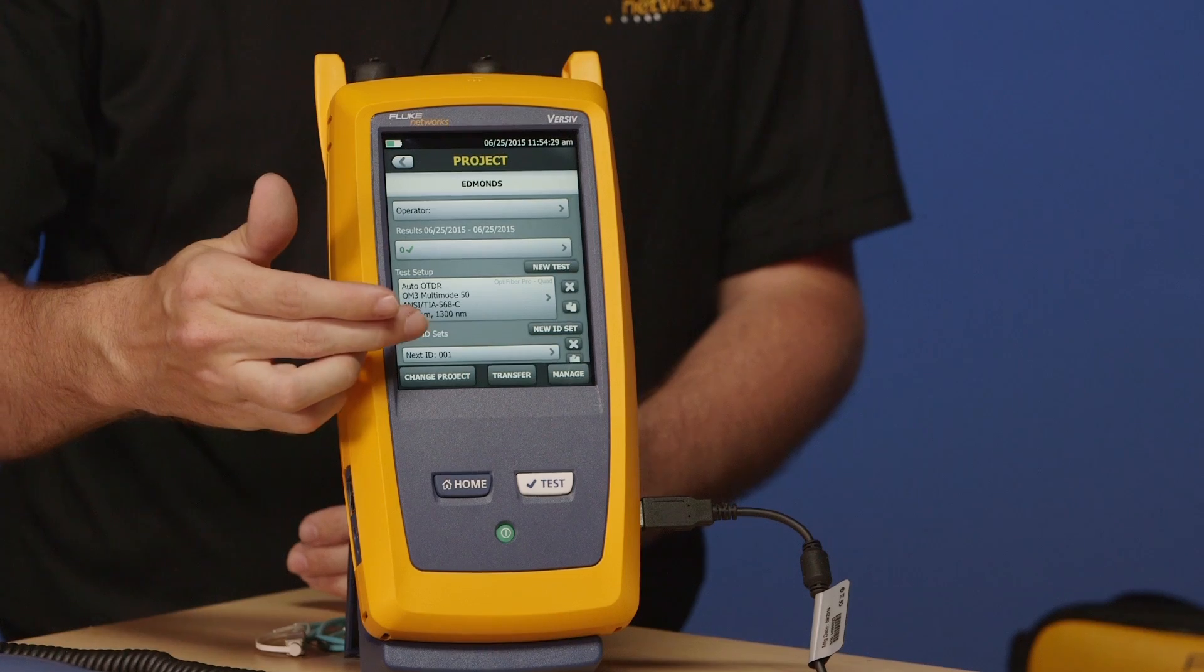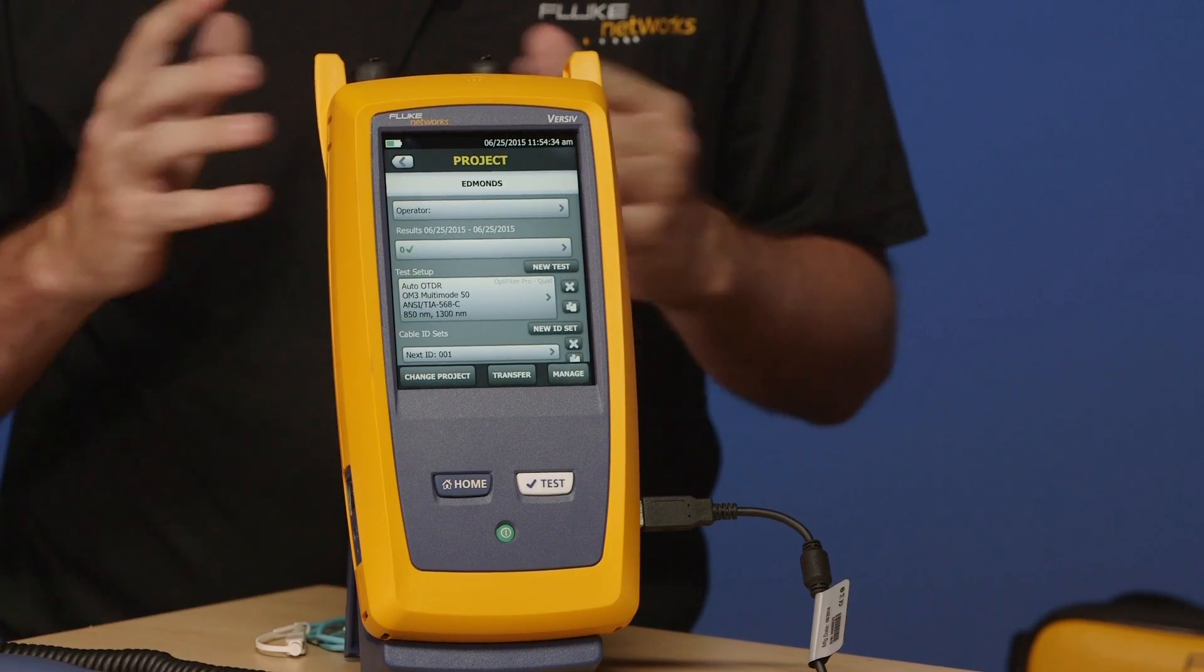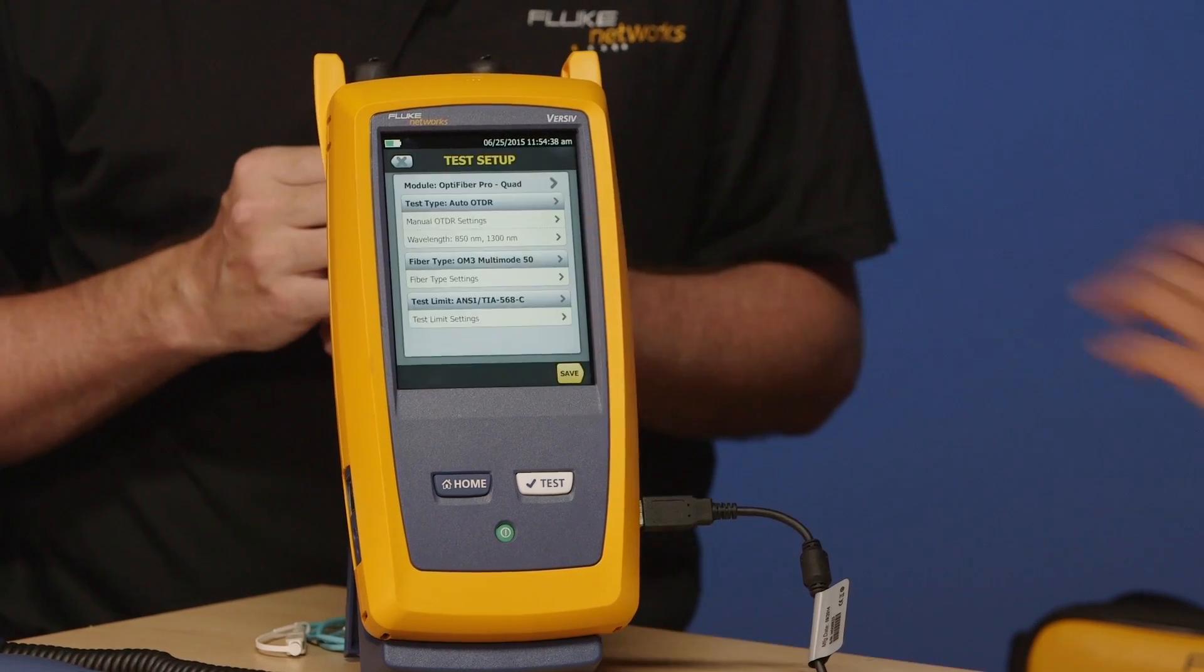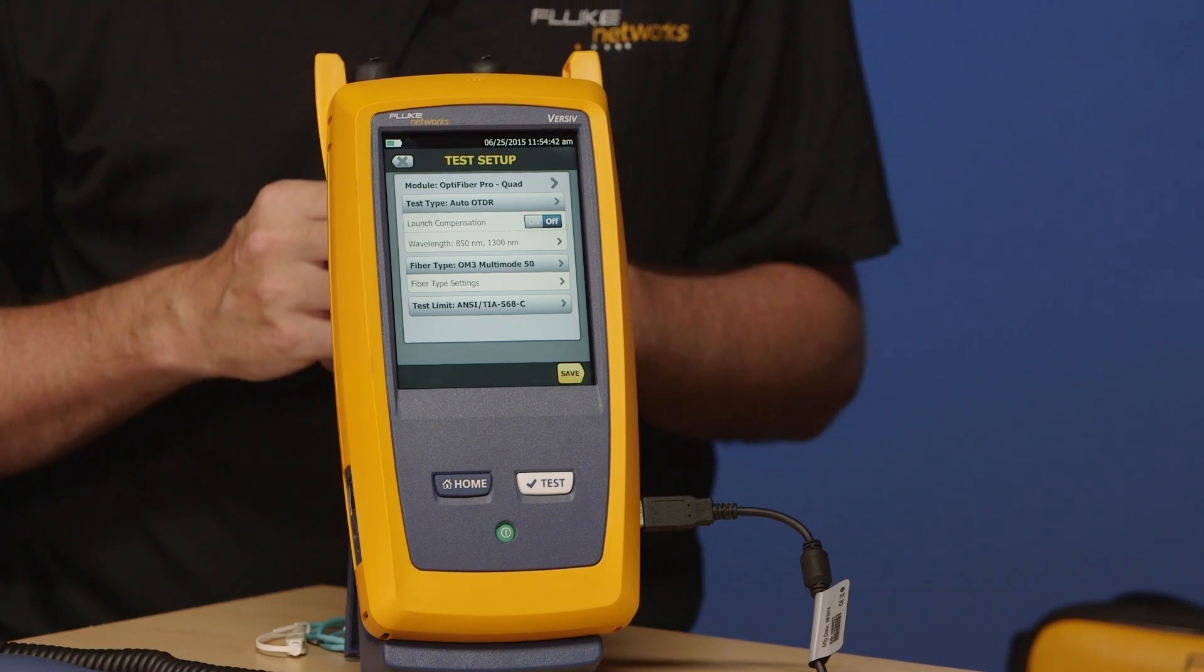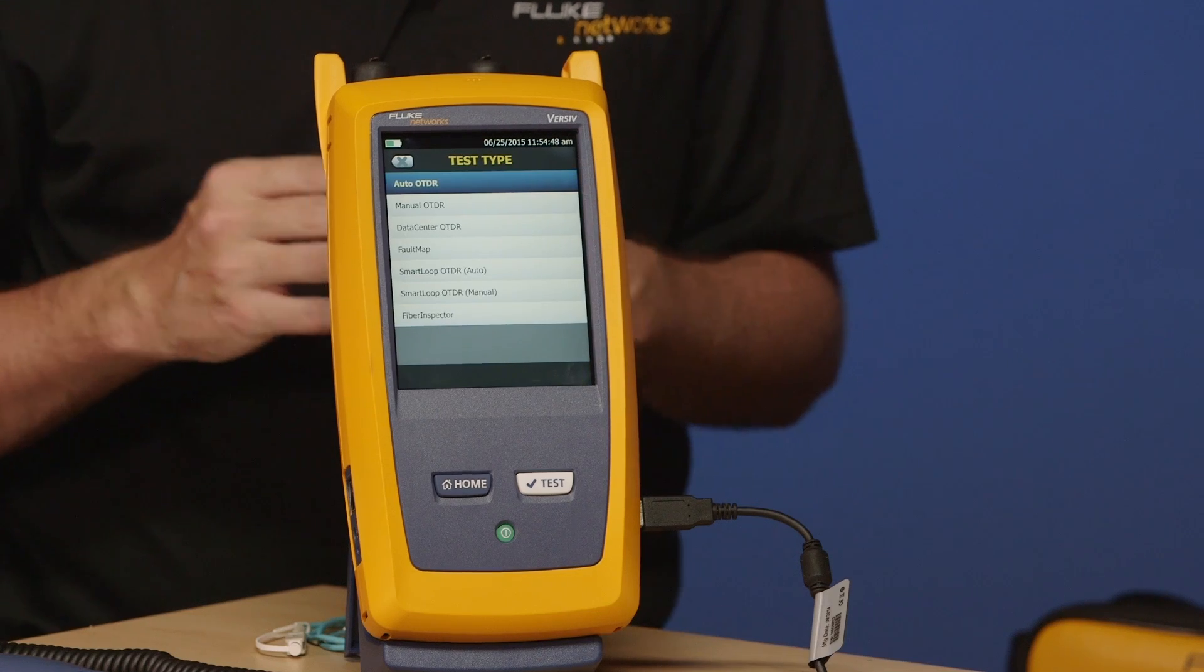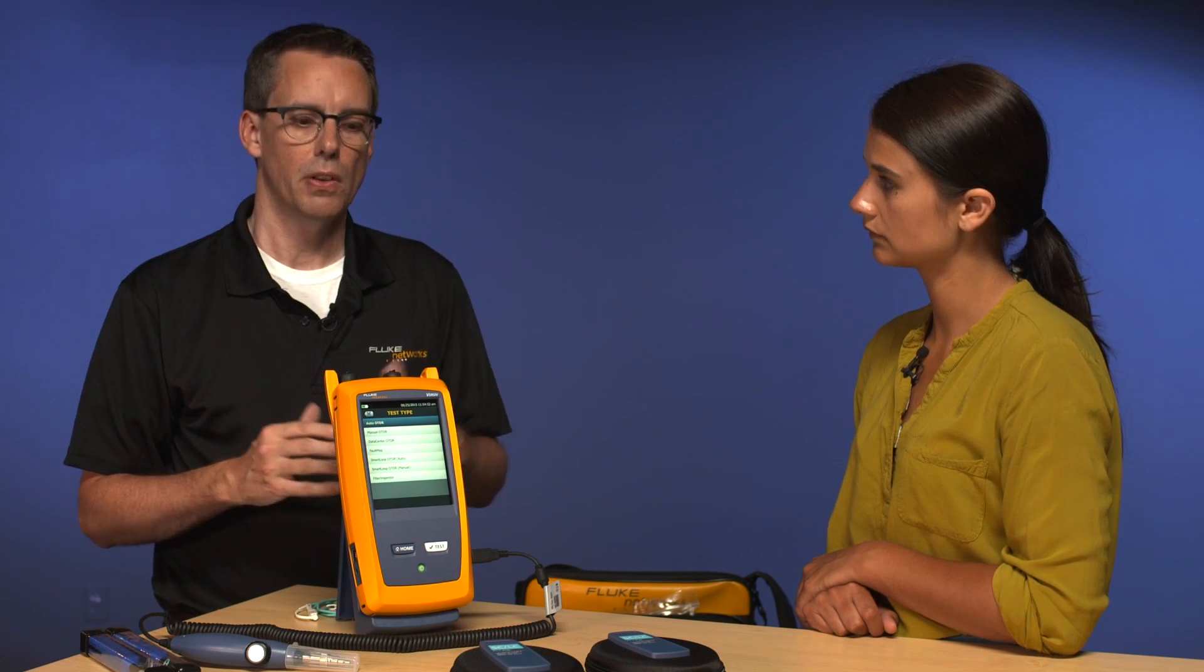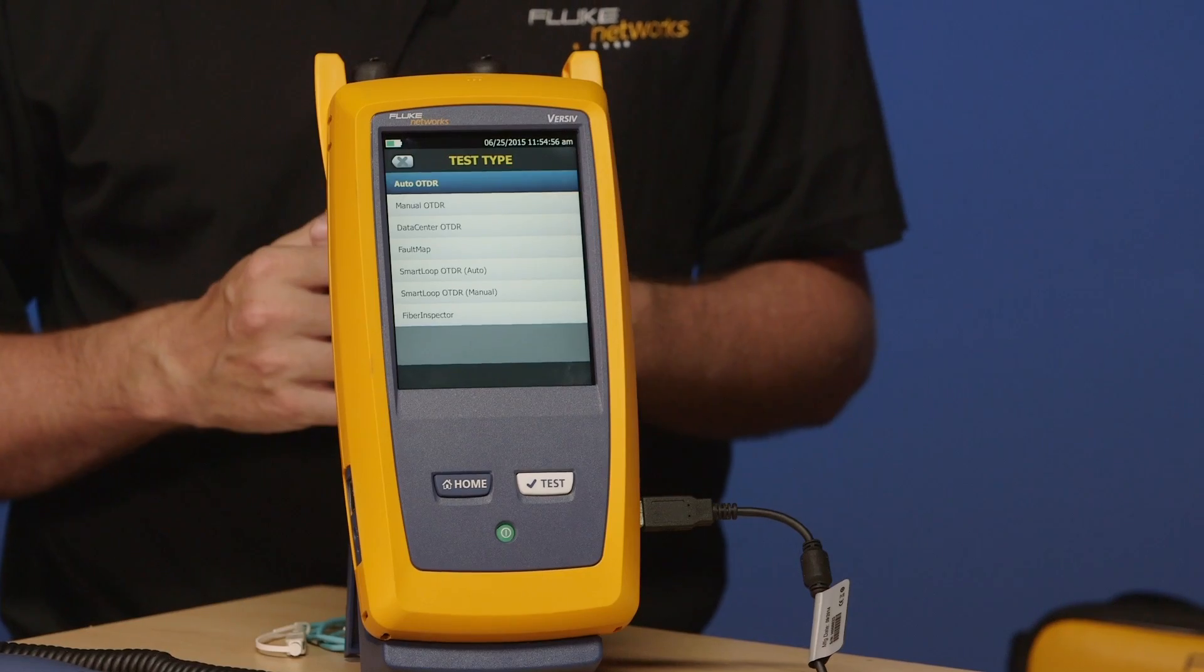Then you get your basic setup. Because we have the OptiFiber Pro module in the back, it's automatically gone to a default OTDR configuration. Let's take a look at that. So the first thing on there is the type of OTDR test. And there are a number of options here, so go ahead and tap on Test Type for me. We're not going to do all of these today. This is just a getting started video. The first option on here is Auto OTDR, which is one of the most common settings.